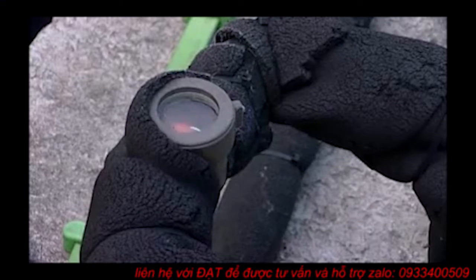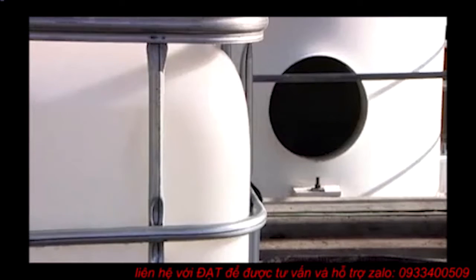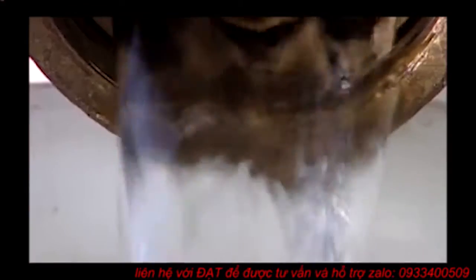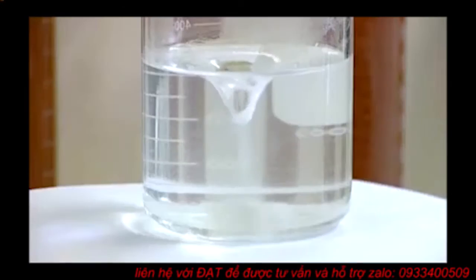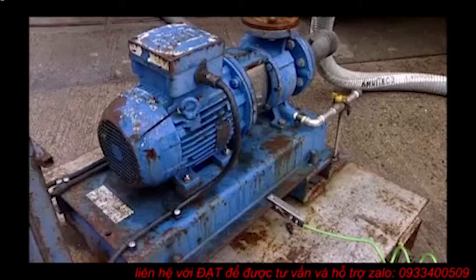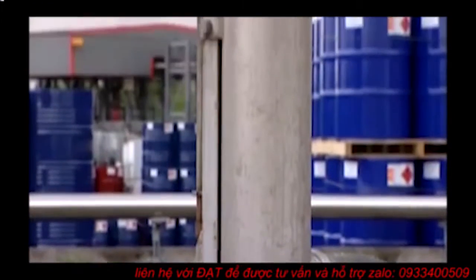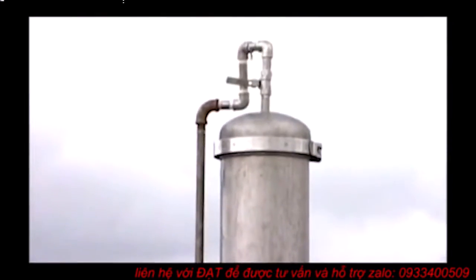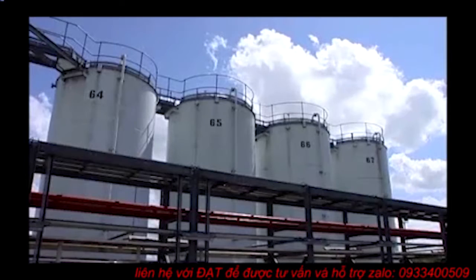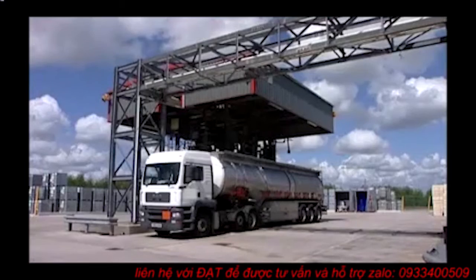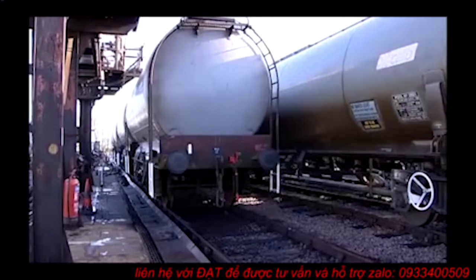Static electricity can be generated in the solvent or on non-conductive surfaces such as plastic drums. Static electricity charge can be generated in solvents by liquid movement such as flow, mixing, pouring, pumping, filtering or agitation operations, where the movement separates electrical charges which may accumulate in the liquid and the containment system, such as pipes, tanks, drums, road tankers, rail cars and ships.